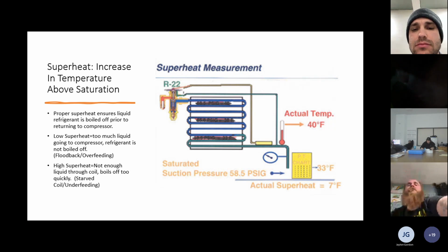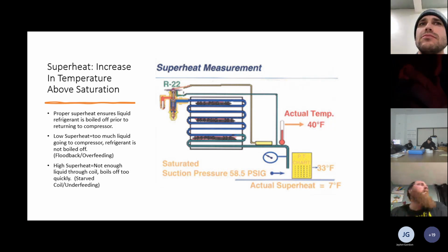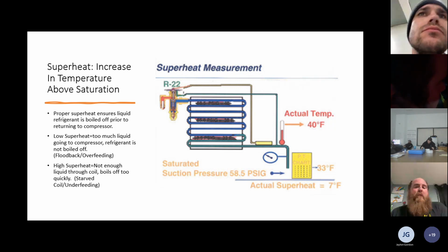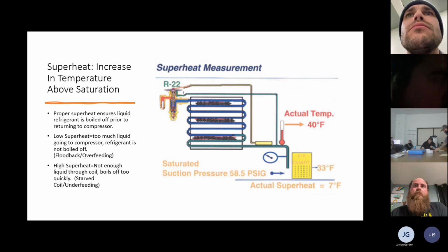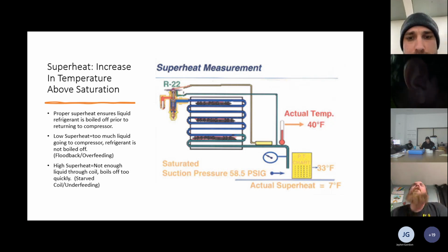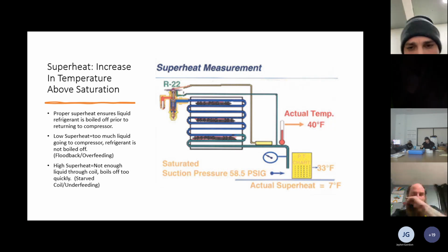I have a question. I was kind of curious why we would wait that long, if your expansion valve, depending on how it's set, your pressure, your temperature of your bulb versus your spring pressure is always still going to be the same. No, because the valve will hunt. The valve's constantly hunting. That valve can constantly move, it'll move 10,000 times. But it's still going to move up and down based off the outlet temperature on your suction line.